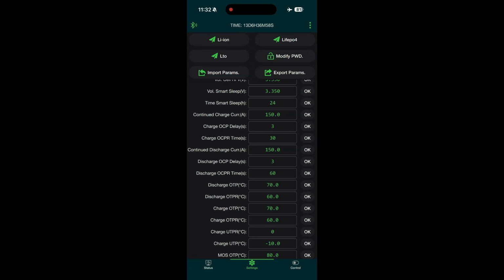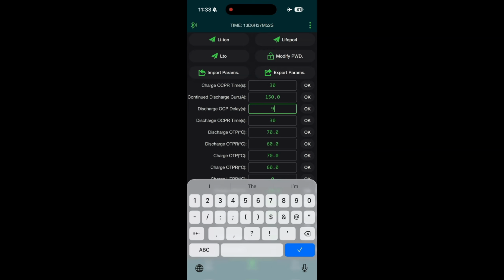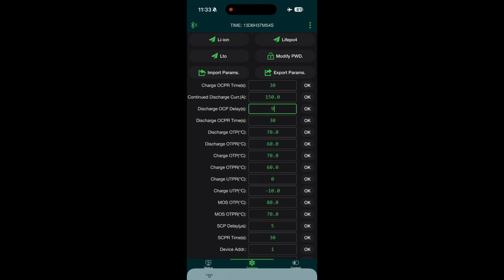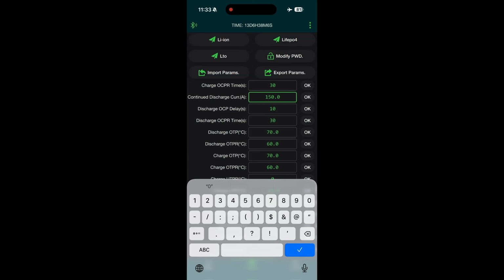Now it's having an issue, so I'm guessing 10 is the minimum. Yeah, okay, so I'm going to set it to 10 seconds. So that's how long the Discharge OCP Delay will be. So it'll wait 10 seconds until the discharge is over 150 amps, and then it'll stop allowing any discharge to come out of the BMS. The next step is the reset time. So how many seconds do you want to wait until it will allow discharge to happen out of the bank again? So again, I'll leave it at 30.